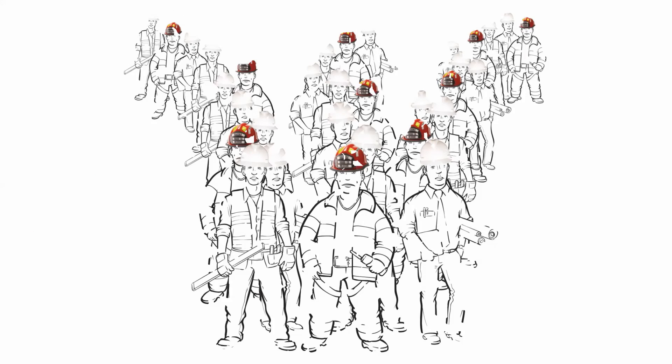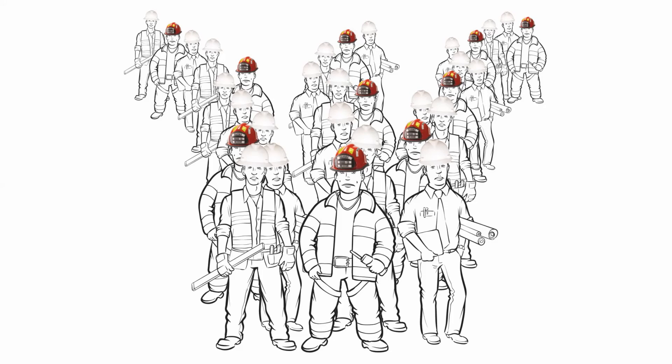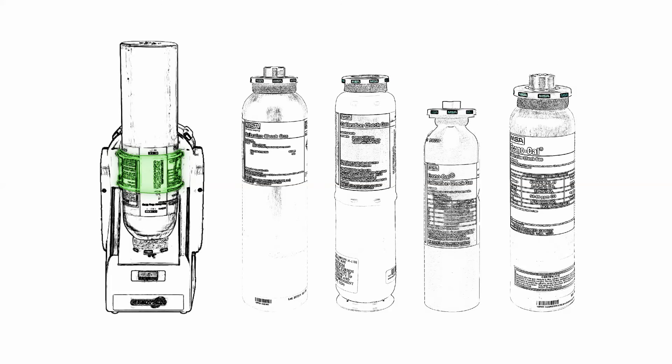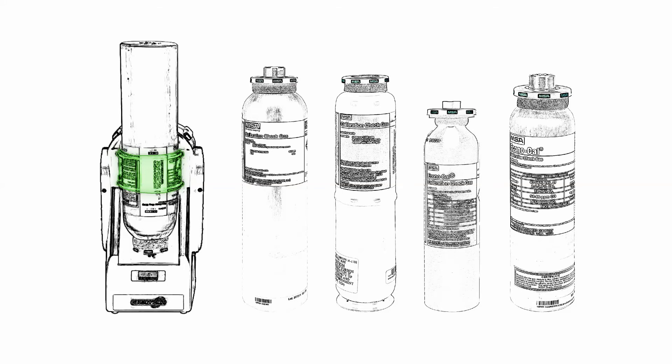No more waiting in a long queue. Bump tests and calibrations are now as simple as leaving the gas detectors on the test stands. Our advanced system will take it from there, including selecting the right gas cylinders, and will notify you when your calibration gases are nearing empty.